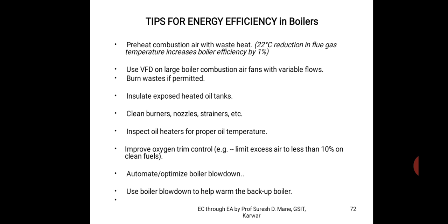A lot of other technologies are shown here. One technology is oxygen level monitoring, related to applied thermodynamics which we teach. In real life, they check the oxygen in the exhaust gas, which should be low. If more oxygen is present in the exhaust gas, it means we are supplying more air than required, and this excess air carries heat away, which is not good. Less oxygen is also not good because we are not burning the entire fuel, while more oxygen sends a lot of heat away as hot air. So there's a trade-off, and almost 10% or below should be the amount of oxygen in the exhaust gas.